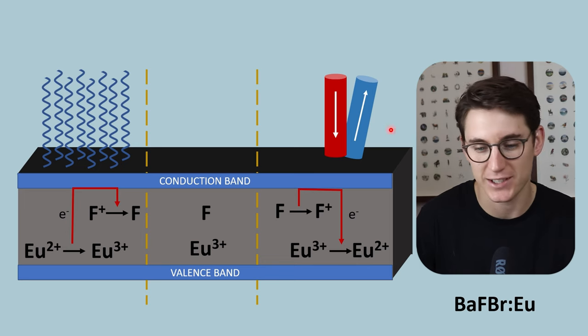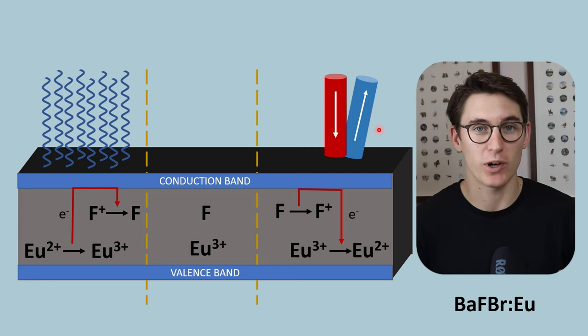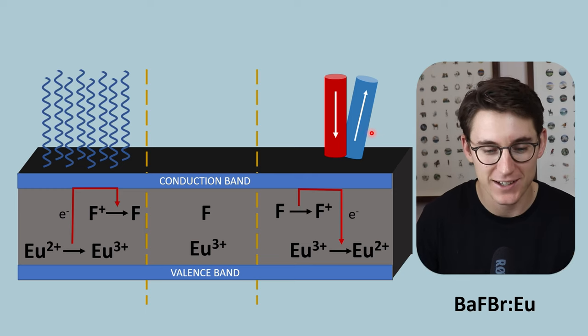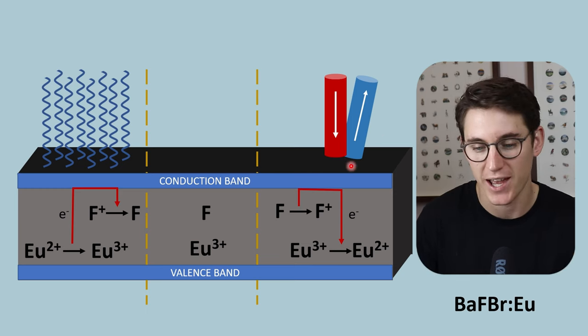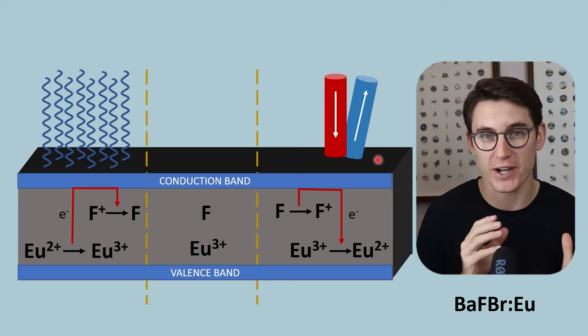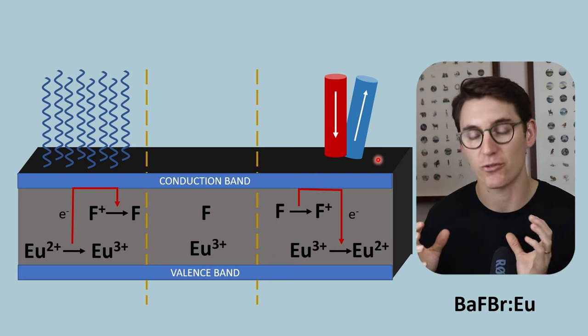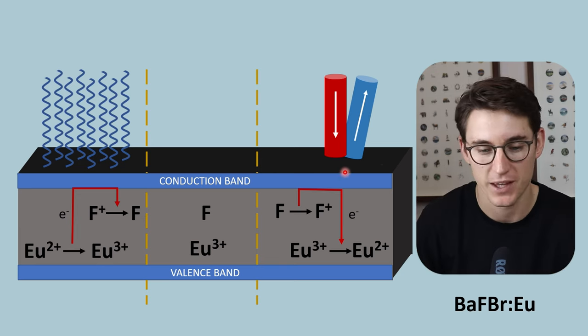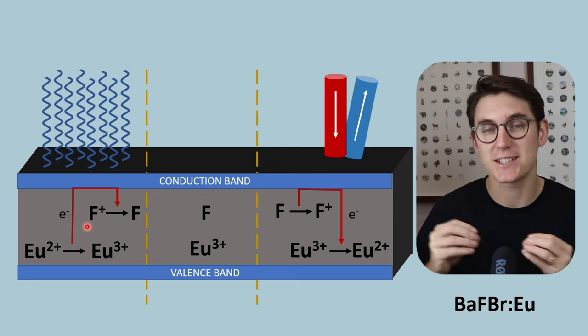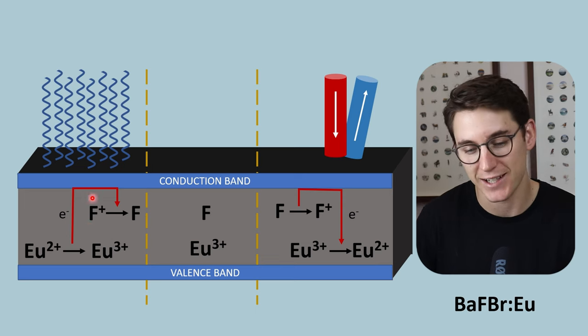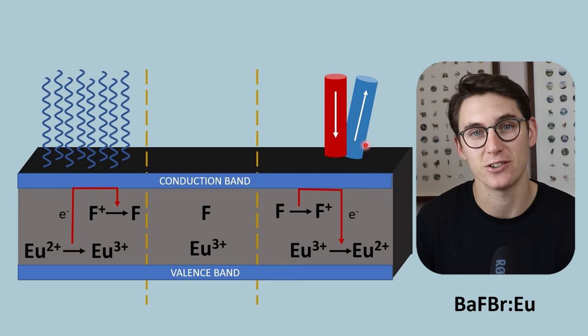The conversion of x-rays into light is known as luminescence. In screen film radiography, the x-ray conversion into light by the intensifying screen was immediate — we call that fluorescence. Here, there is a delay between the x-ray exposure and light production, and that delay means this process is called phosphorescence. There is a key difference: fluorescence is immediate conversion of x-ray to light, while phosphorescence involves a delay before light is produced. When x-rays hit our cassette there is actually some fluorescence happening, but it doesn't contribute to image production — the phosphorescence, the delayed production of light, is what gives us our signal.